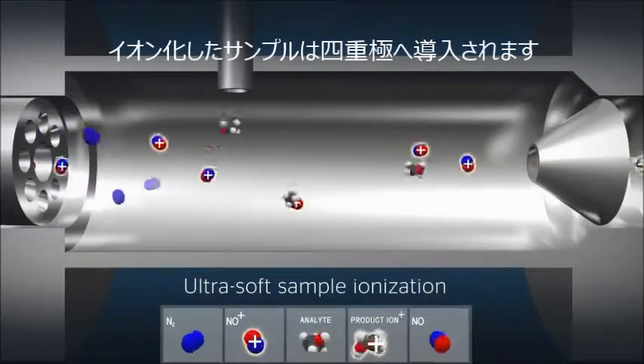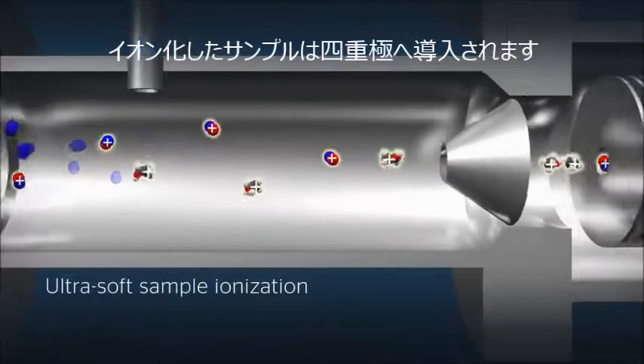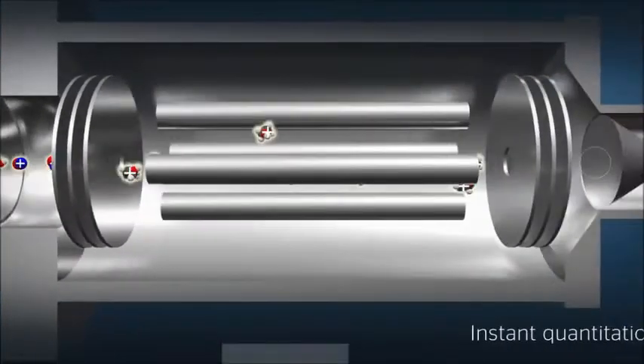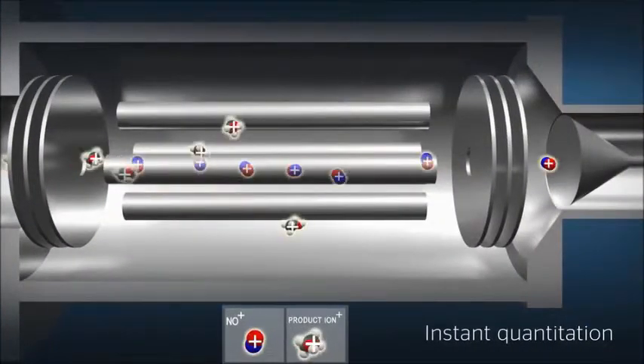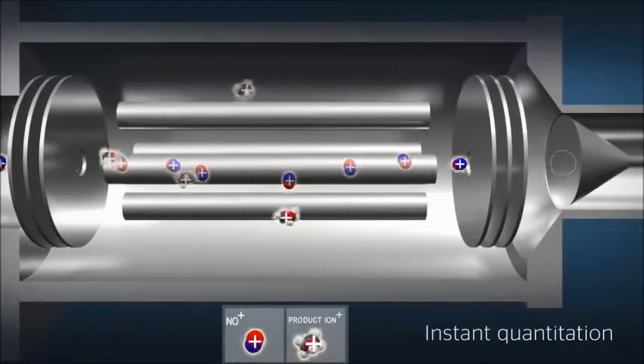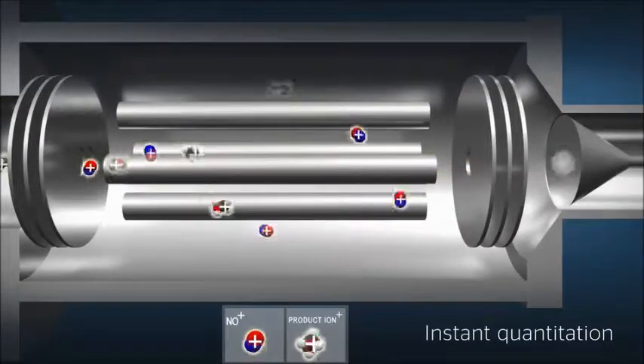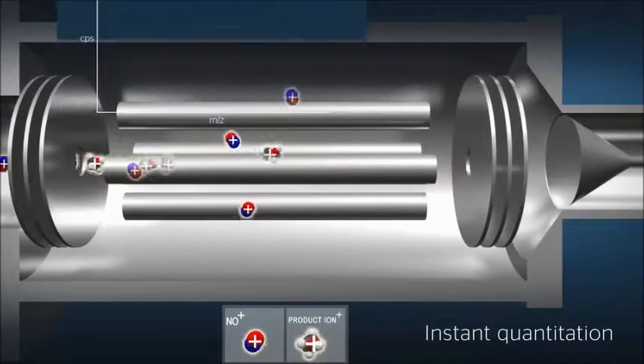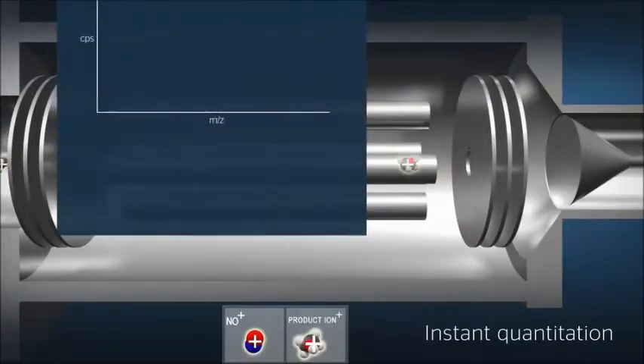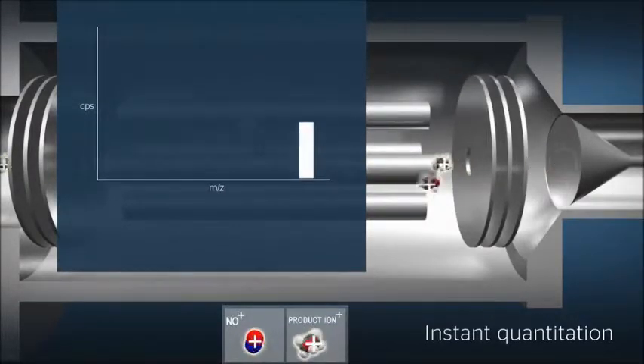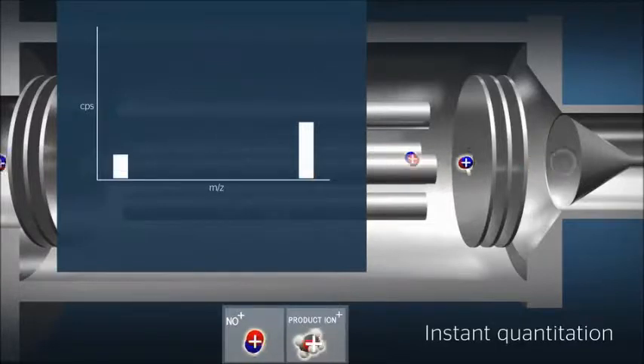At the exit of the flow tube, product and reagent ions are focused into a second quadrupole. All ions are transmitted in sequence to a detector and the resulting signal is recorded for each. This data is processed in real time with the chemical information in SIFT's extensive compound library.